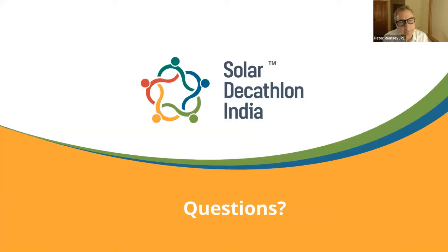Just to give the attendees a sense of the numbers in India, typically these could be as bad as 150 square feet per ton or going up to 400 square foot per ton. And the question is, how do you reach a value of greater than 800? You need to go through the solar decathlon modules again. Do all of them right, you'll reach 800 square feet per ton.